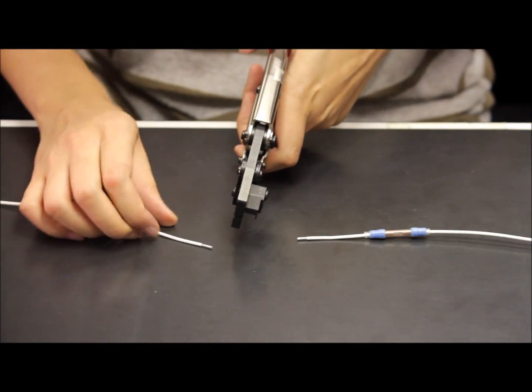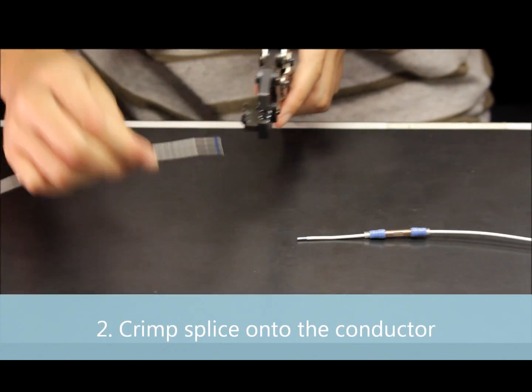Place the crimp splice into the crimping tool and insert the wire until the conductor is visible through the inspection hole. Crimp the splice onto the conductor.